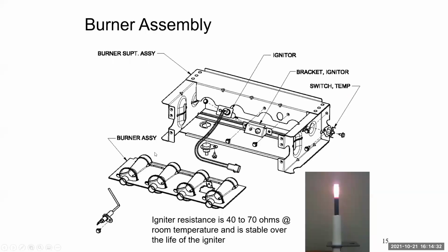So burner assembly, I'm just touching base on your burner assembly. One thing I'll point out here, and it's going to repeat itself a couple times, is your igniter resistance. It's the same for all Carrier furnaces, 40 to 70 ohms on your igniter at room temperature. They don't take a long time to cool down once you shut down, but give it 3-4 minutes before you check it if it's been fired up or had flames running across it.